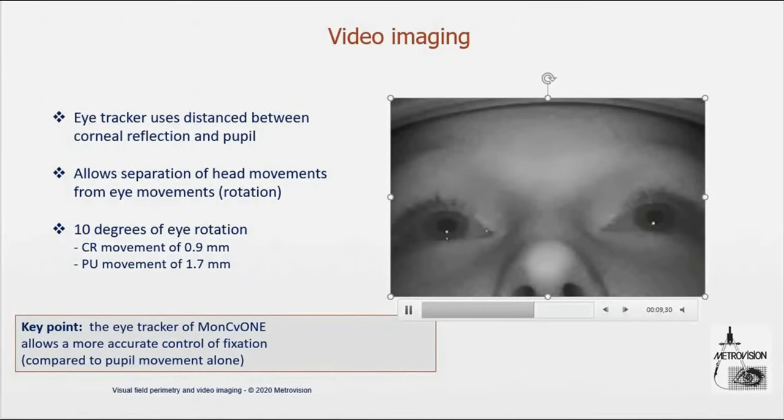The camera is not only a wide-field camera, but it's also with high resolution. The advantage of high resolution is that it allows you to monitor more accurately the fixation. Looking at this image, you see the pupil, and also you see this little bright spot, which is a corneal reflection.